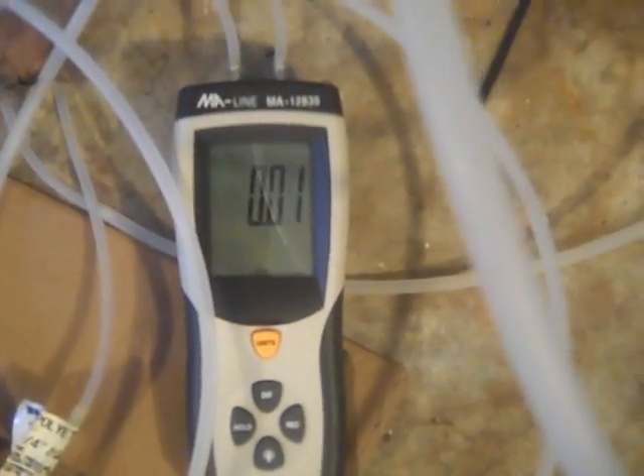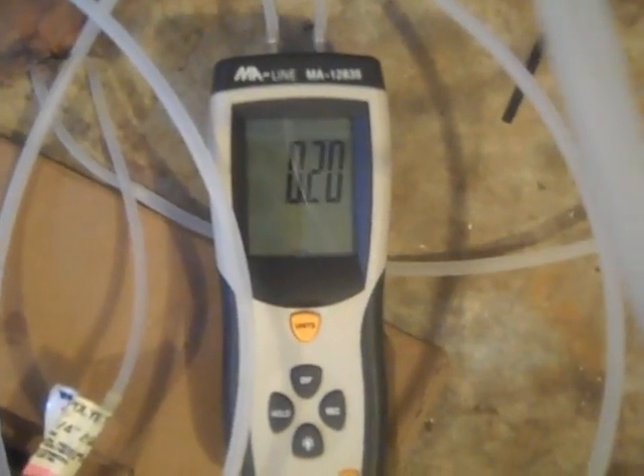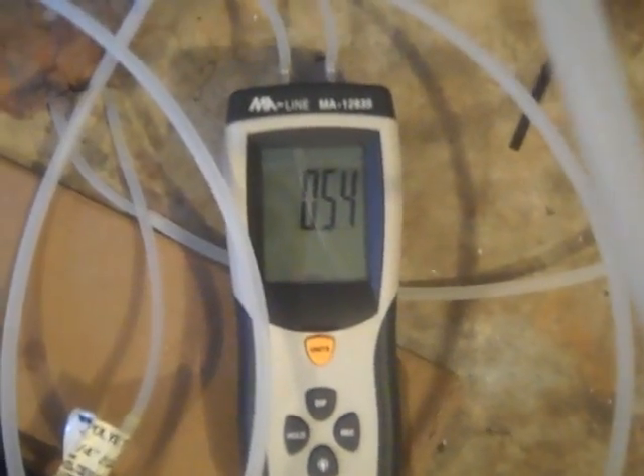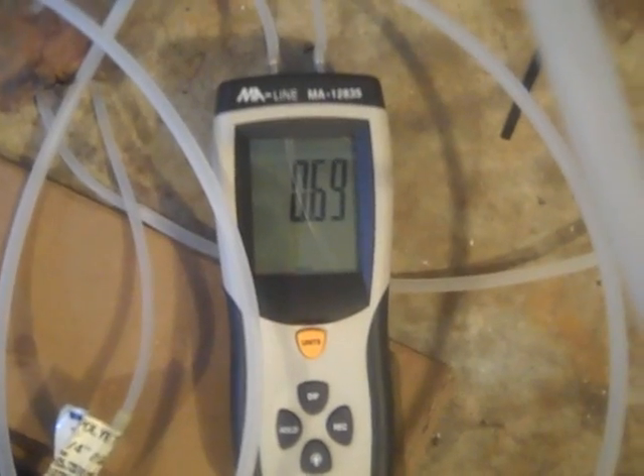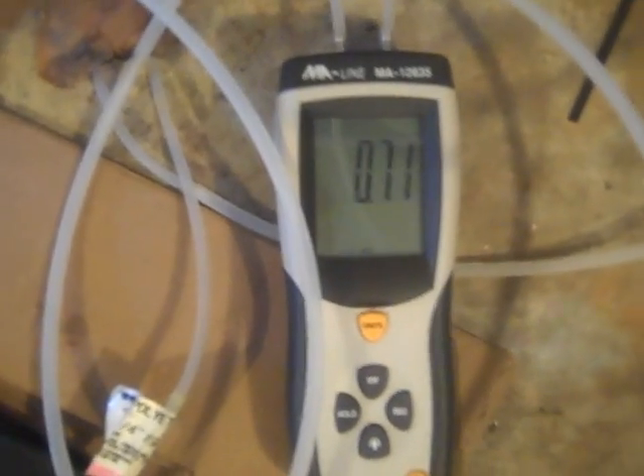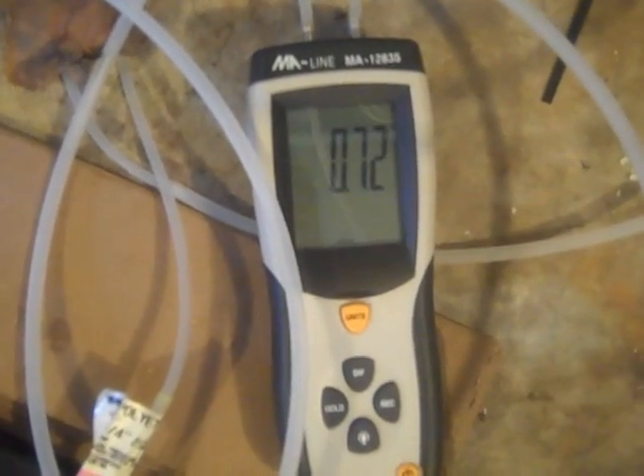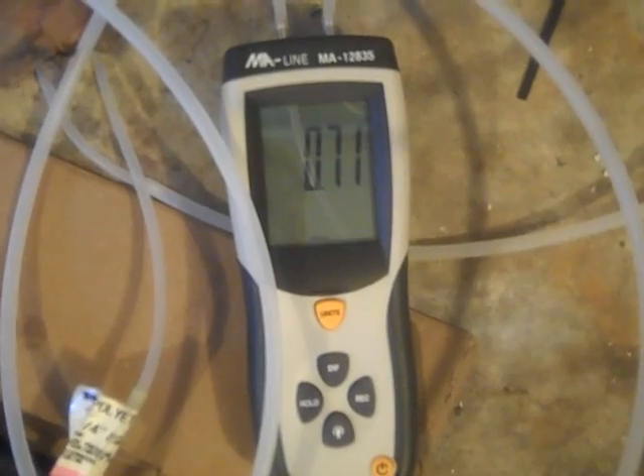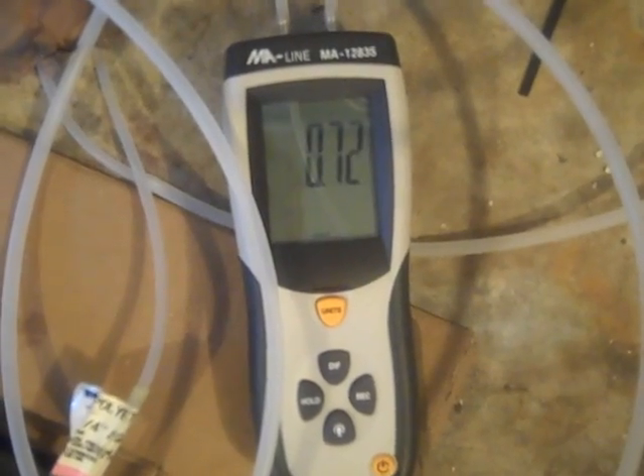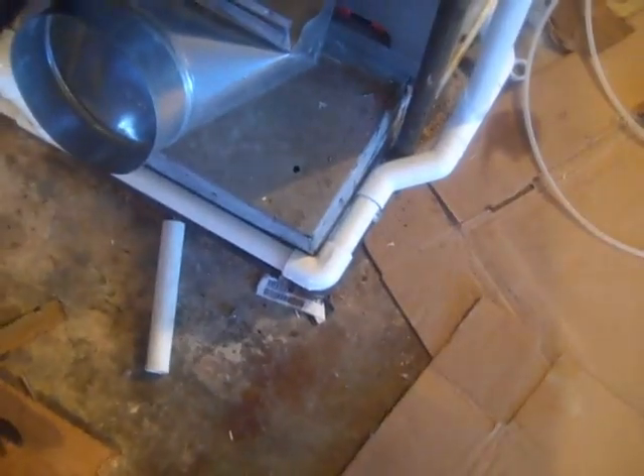And this is the most accurate way to determine your airflow. You can do a temperature rise test as well, and I will be doing that because I want to make sure, once I fire the furnace off, that it is within its temperature range. Look at that, .72 for medium high. And I did this before through the plenum and that hole there. Of course, that was on the other side of the coil.